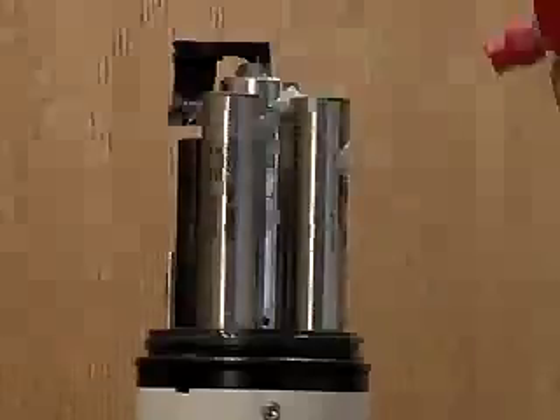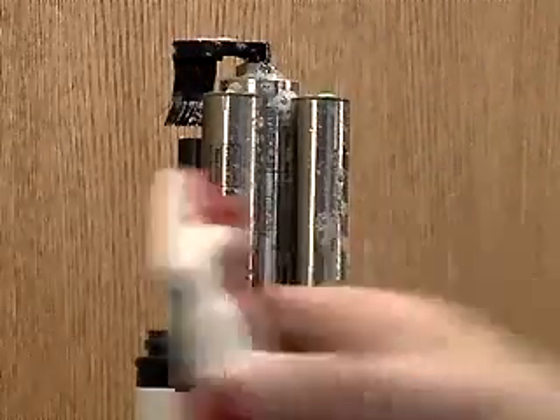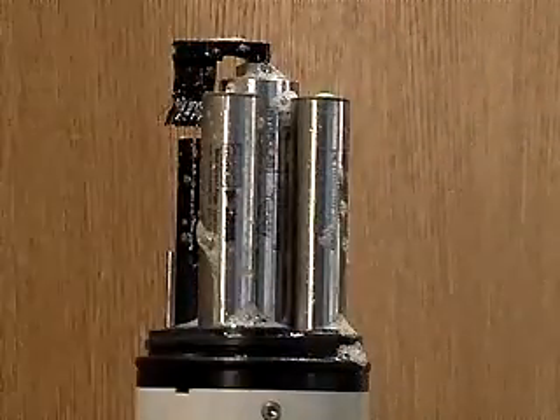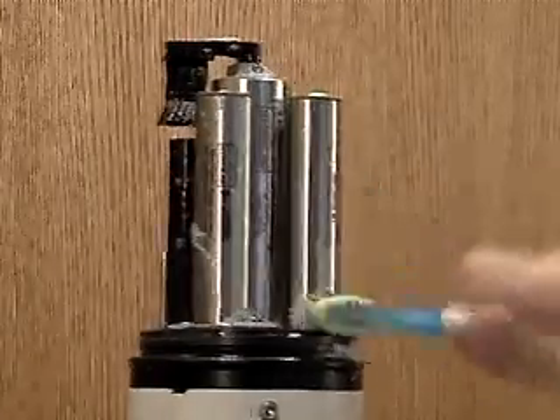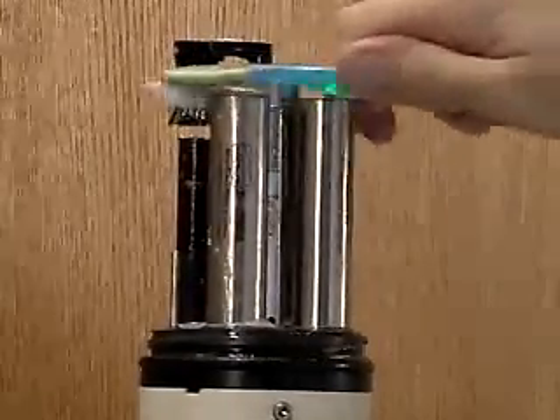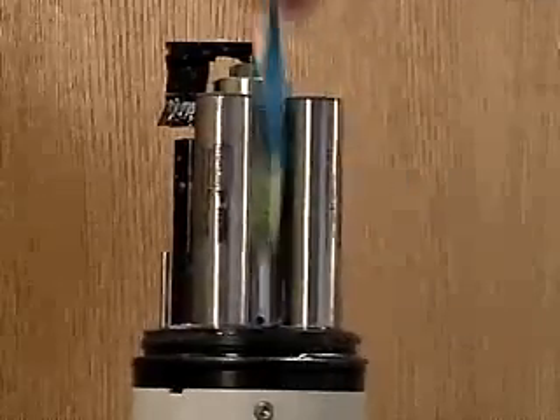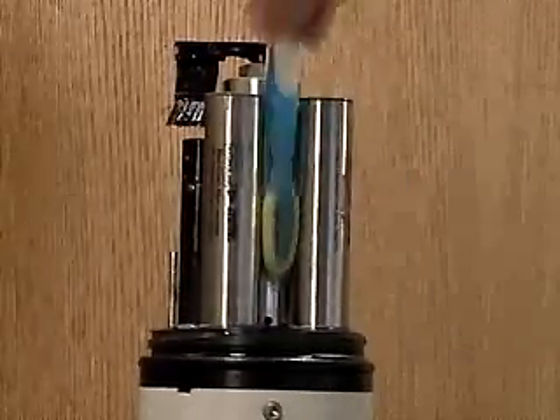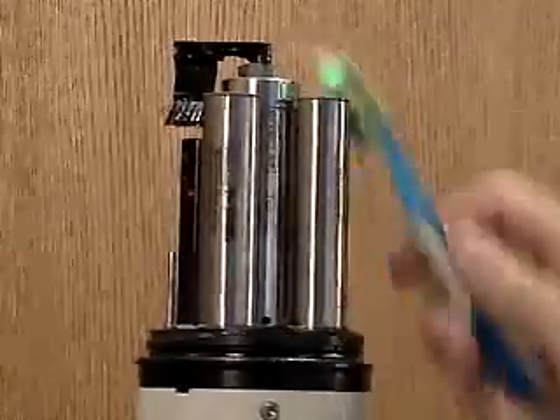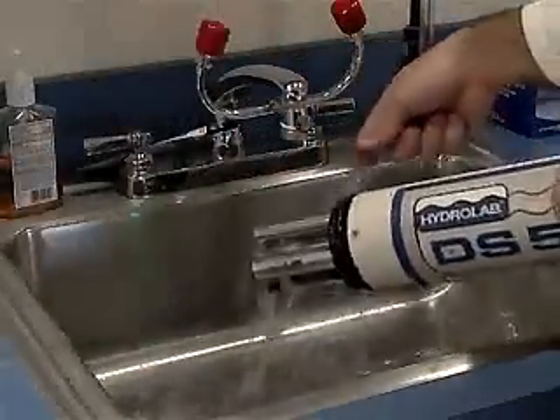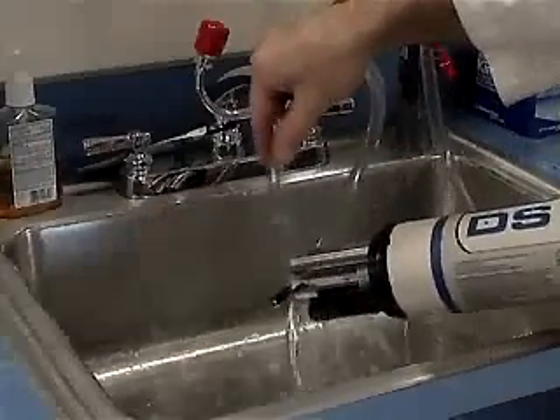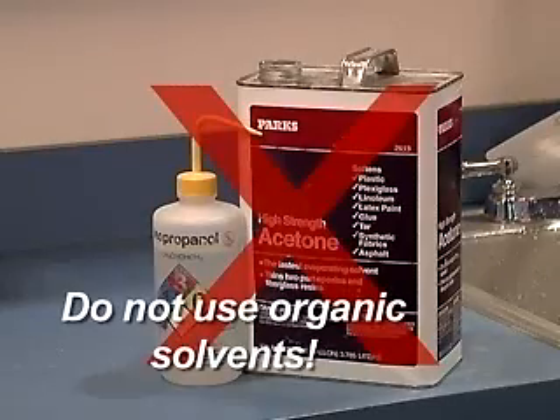Maintenance. The only maintenance required for the fluorometers is to keep them clean. As optical sensors, it is very important to give them a clear field of view into the water sample. Before and after each deployment, use a soft brush and mild soap to remove dirt and debris from all of the sensors. Rinse with clean, fresh water. Do not use organic solvents such as methanol or acetone to clean the sensor. These chemicals will damage the plastic components of the sensor.